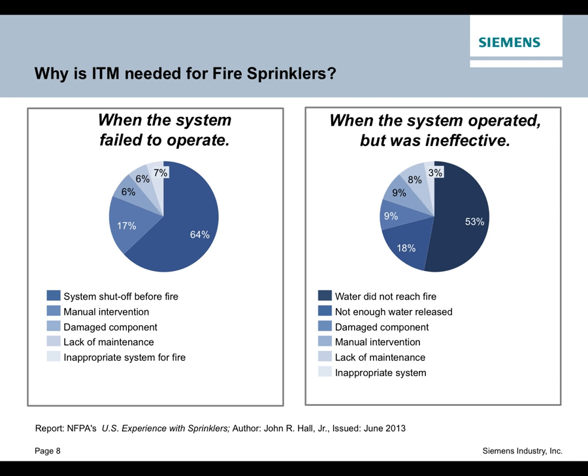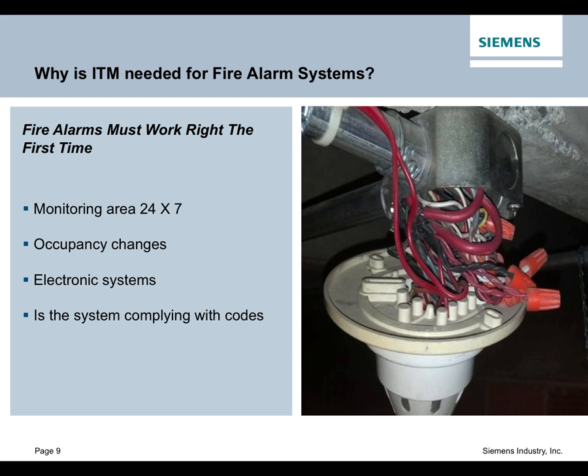Now on the fire alarm side, you don't get the same type of statistics that we have on fire sprinklers. But, as I mentioned before, the fire alarm system must work right the first time. You don't get a second chance with these systems. The fire alarm system is electronic. It's monitoring the atmosphere, in the case of smoke detectors, 24 hours a day, 7 days a week. And you need to make sure that those things are addressed and tested to make sure they're performing well. We talked about the occupancy changes that may be occurring. And by doing the preventive maintenance inspection work, you'll find whether or not the system is still complying with the codes. The picture that we show here is showing a bad case scenario. It's showing a picture of when somebody did not install things correctly and there was a poor workmanship issue.